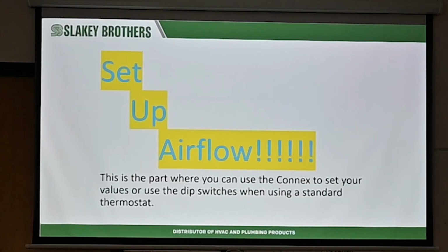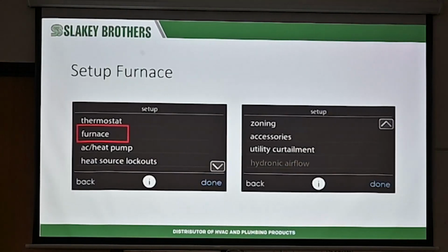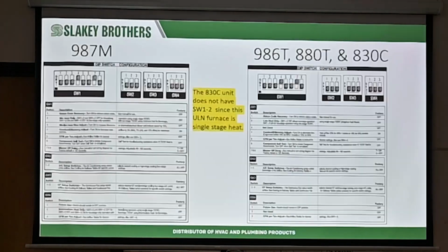All right, furnaces, the other major thing is airflow. In the Connex controller, we're going to go over airflow, how to set it up through the Connex. But because our Evolution furnace, 987M, 986T, the 880, they all can work with a regular thermostat, you can hook it up with the regular 2-stage air conditioner or no air conditioning at all. Because they can work with a regular thermostat, I did some stuff here about setting up airflow. Make sure you consult each particular unit in the dip switches.